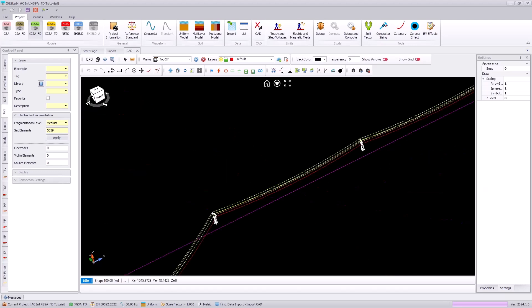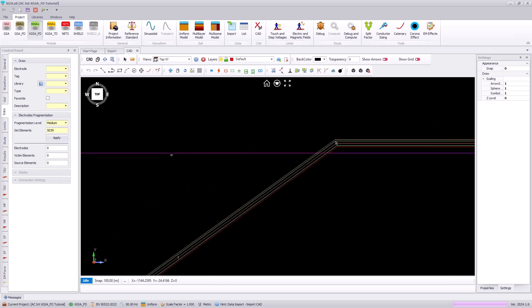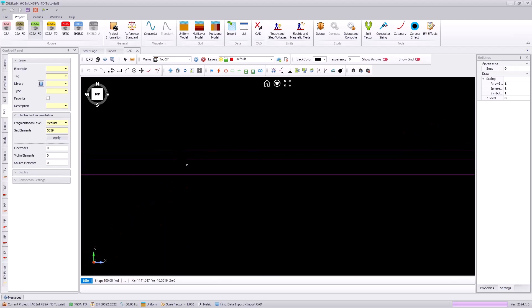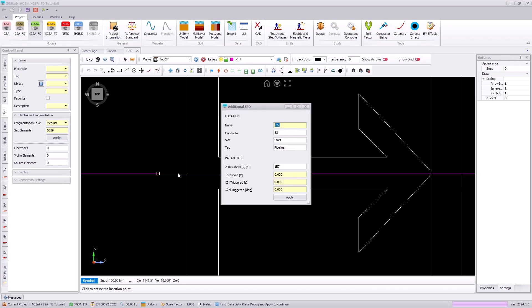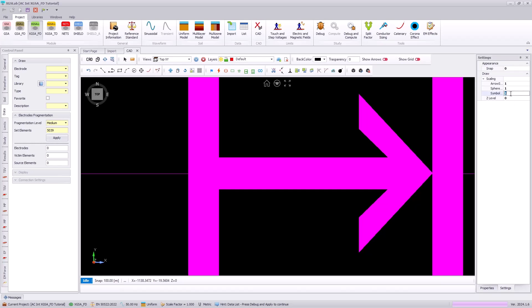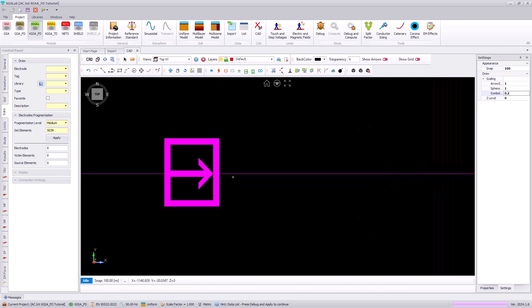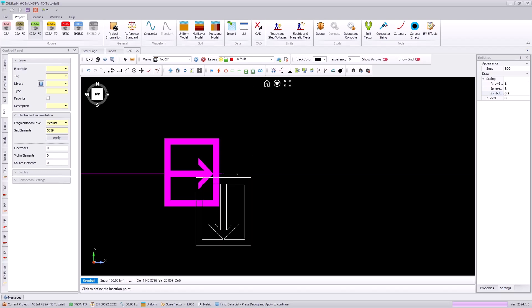Following the tutorial documentation, the next stage of our analysis we need to import or create some longitudinal and transverse impedances. We'll go to a small section of our pipeline and insert a longitudinal impedance. This will be called Joint A, and this represents a surge protective device or arrestors on our pipeline to help reduce the exposure area. For this we will use a 650 volt threshold and a 0.001 ohm impedance. We will reduce the symbol size for a clearer visual representation.